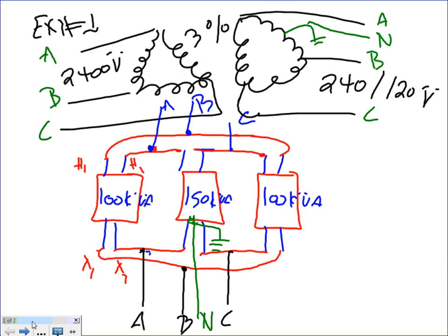The three-phase kVA is basically the contribution of every transformer at 100 kVA level. So if I want this system to pump three-phase kVA, I want this one to pump 100, this one to pump 100, and this one to pump 100. That will be the 300, the kVA contribution of three-phase kVA. If you want three-phase out of this transformer at 150, can this transformer pump 150 kVA? Can't, doesn't have it.